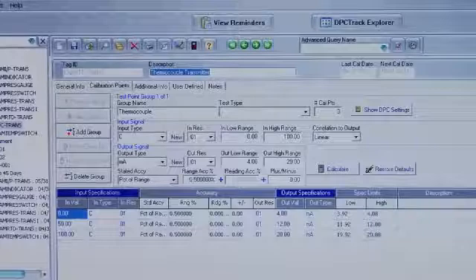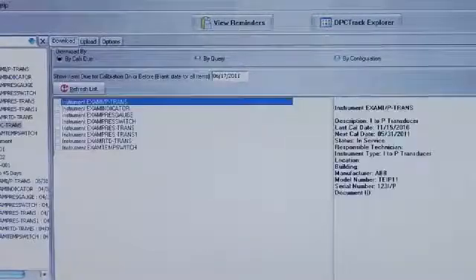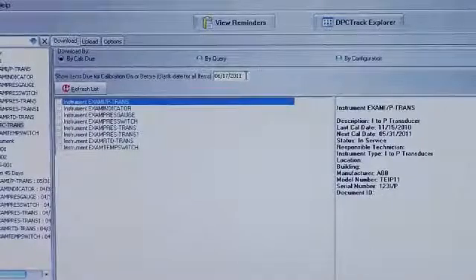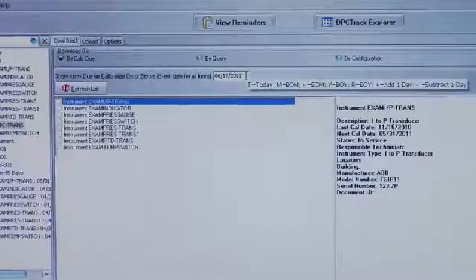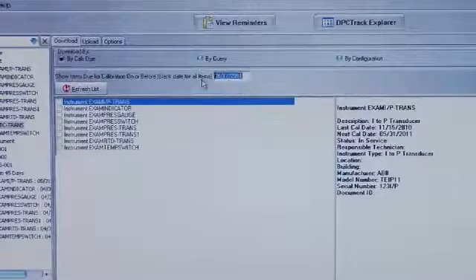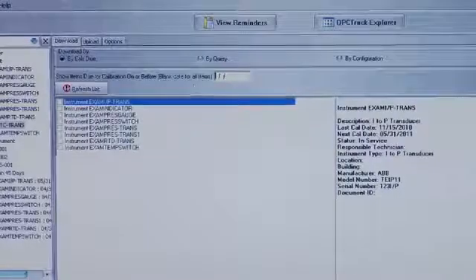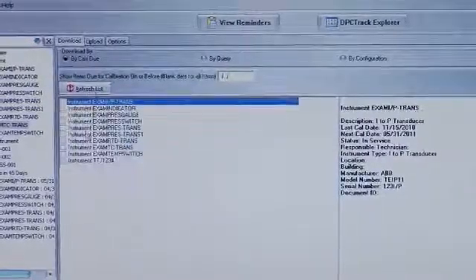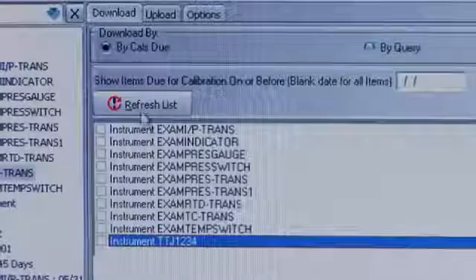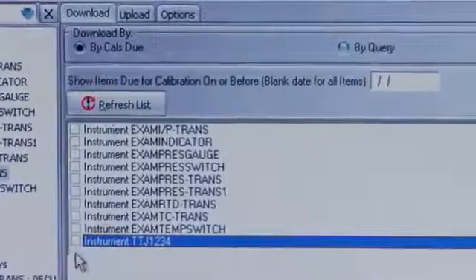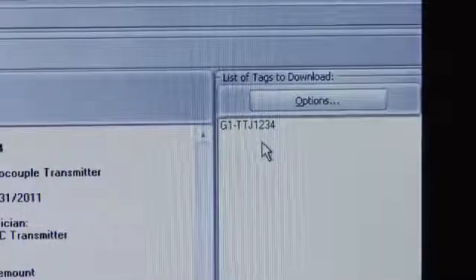To load a tag into the calibrator, select upload download, and here you can see the tags that are due or overdue by a certain date. To see all the tags, clear out that date and refresh the list. Here you can see the tags that are available to load into the calibrator. By selecting a tag, it's loaded into the tags to download box. This tag is now ready for download to the Fluke 754 calibrator.